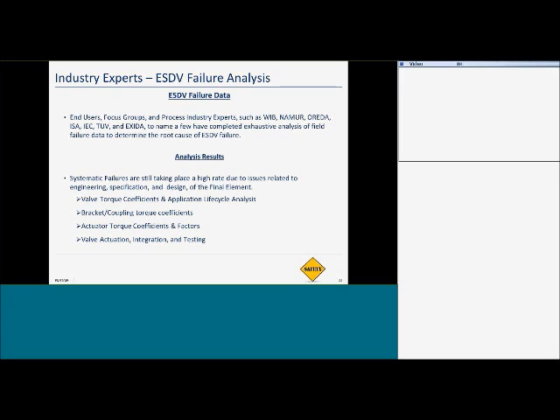Second of all, they determined that they had a lot of bracket and coupling and really drivetrain component failures of one kind or another. This could be due to a lot of issues, under-engineered bracketry. When we're talking about some of these ESDV applications, we've got large, high-pressure metal-seated ball valves with very robust shafts and a massive actuator to actuate that valve. And now you've got to make sure that the bracketry and drivetrain components are designed sufficiently to handle the loads and the stresses.